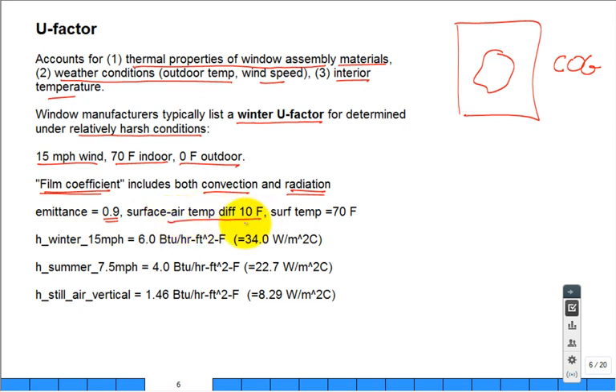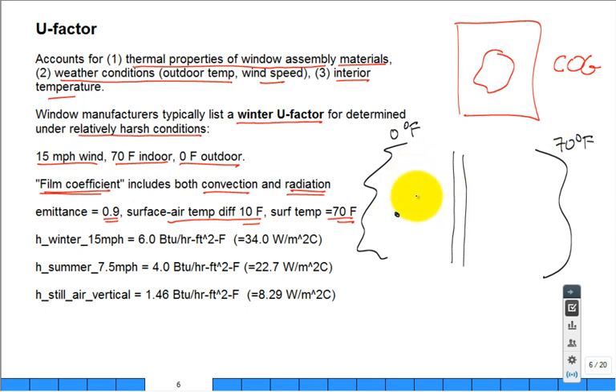It's determined under fairly harsh winter conditions. Not the most severe - 15 mile per hour wind on the outside, 70 degree F indoor air temp, 0 degree F outdoor air temp. What's happening on the inside? It would be like inside this room. What is the convection coefficient? We don't have 15 mile per hour wind in this room. It's pretty much still air but there is some movement, some natural convection.